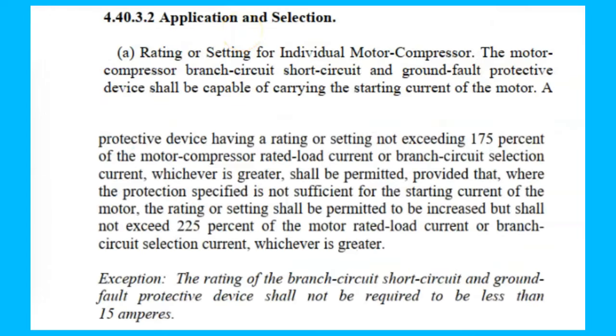Ang sabi sa 4.40.3.2 ng PEC, this is for application and selection. This is for rating or setting for individual motor compressors. So, a protective device having a rating or setting not exceeding 175% of the motor compressor rated load current or branch circuit selection current, whichever is greater, shall be permitted, provided that the protection specified is not sufficient for the starting current of the motor. And then the rating shall be permitted to increase but shall not exceed 225% of the motor rated load current.